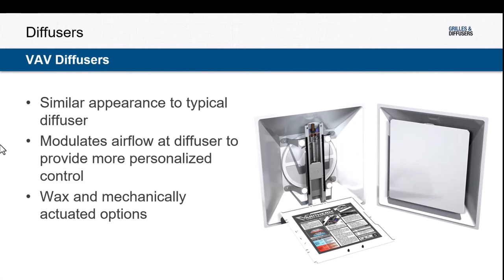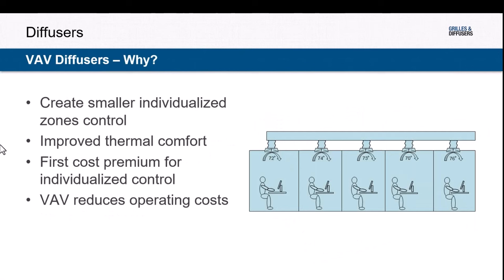Modulating diffusers and VAV diffusers provide an extra level of control with a similar appearance to a square plaque. Air volume is controlled directly at the diffuser by modulating components within the diffuser — this can be done electronically or with wax actuators. Modulating airflow directly at the diffuser gives the ability to create more individualized zones, accommodating different perceptions of thermal comfort. There is a premium cost associated, but it does give a lot more flexibility in achieving thermal comfort.